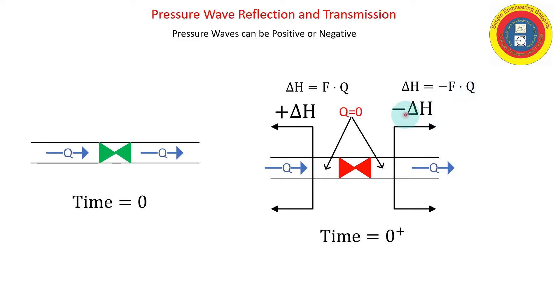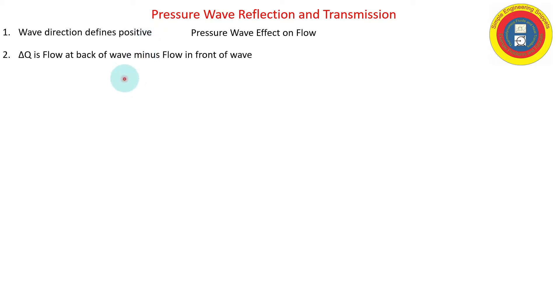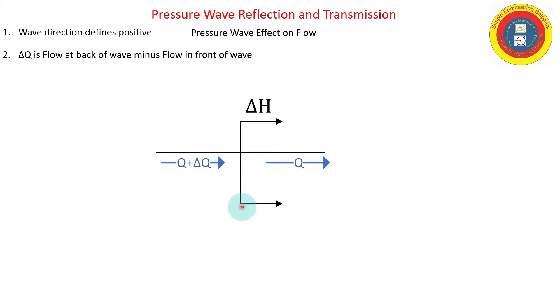The wave propagating downstream must be negative to bring the flow to zero. To avoid confusion, here are two simple rules: first, the wave direction defines positive; second, delta-q in the Joukowski equation is defined as the flow at the back of the wave minus the flow in front of the wave.